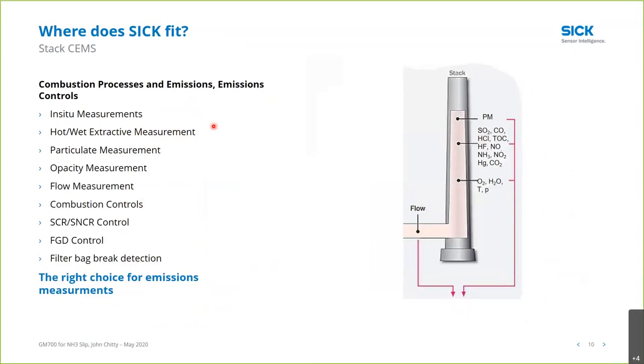So continuing with where does it fit? Combustion processes and emissions controls. So any place around a stack, an SCR, we do FGD controls as well. With the GM32, it measures SO2. So we can provide a feed-forward control to lime injection. SCR, SNCR controls, combustion controls, flow measurement on the stack, opacity, particulate measurement, hot wet extractive CEMS, cold dry extractive CEMS, and we can do both in situ and extractive measurements. So in the emissions world, this is kind of who we are.